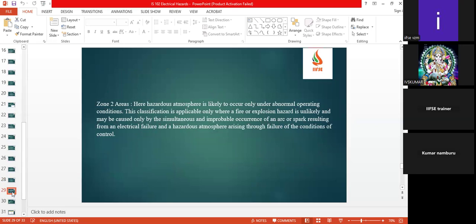Then zone 2. Here the hazardous atmosphere is likely to occur only under abnormal operating conditions. Maybe an incident happens or a leakage happens. This classification applies where fire and explosion hazard is unlikely and may be caused only by the simultaneous and improbable occurrence of an arc or spark resulting from electrical failure, and the hazardous atmosphere arising through failure of conditions of the controls. Sometimes, in case of any control failures, this kind of atmosphere can also create an issue.